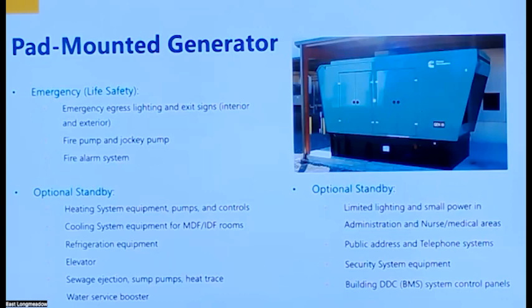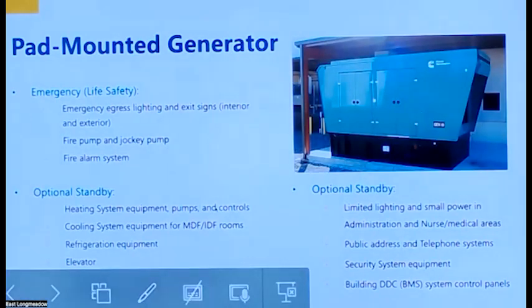And it will be the source of backup for emergency life safety loads. In this case, this is the emergency egress lighting, exit signs, also the fire pump, if we will have a fire pump, I don't know if we know that for sure yet, and also the fire alarm system. And also what we call standby optional systems, and the majority would go to the heating system and associated pumps and controls. Also the cooling system for MDF, IDF rooms, the refrigeration equipment, the elevator, the sewage ejection, sump pump, heat trace, whatever we will have. Also the water service booster, you don't see it, it's right below that line, but I see it on my other screen.